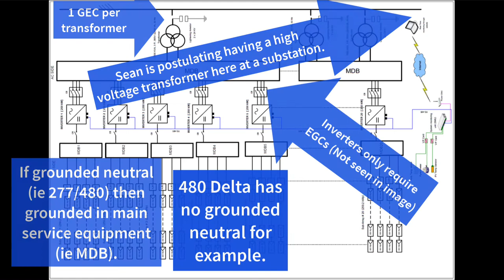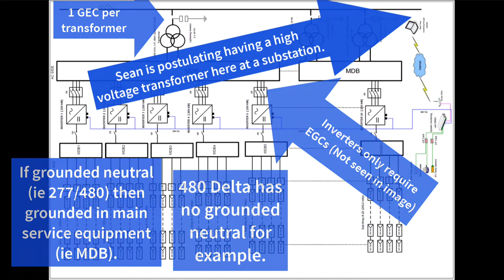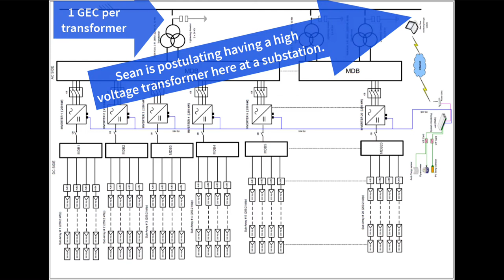You know, so if the transformer took you from whatever the voltage is, let's say 690 volts AC or something like that, or 600 volts AC, or even if we have some 1000 volt AC equipment or 800 volt AC equipment, could take you up to 34.5 kV. The whole plant might be a 34.5 kV plant, and in that case, there would just be some large switchgear that would combine multiple 34.5 kV circuits. And then at that point, in most cases, your service is actually at 34.5 kV. It's not at 800 volts or 600 volts or anything like that.